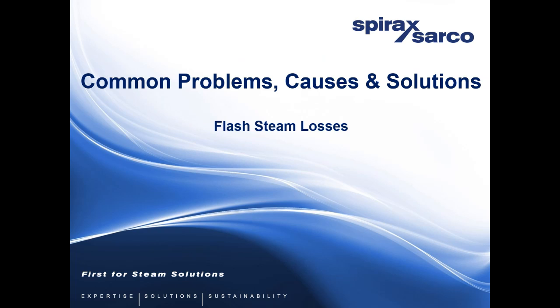The first question is, I have a Vapomat coil boiler that's 600 kgs per hour that is building up scale more frequently. The feed water is tested and it is soft water. What could be the cause of the blockage? So building up scale, you've got salts that are adding in there. So the water softness could be the issue there. You're finding that you're getting salt added into your system. Could be the lack of blowdown or lack of TDS control.